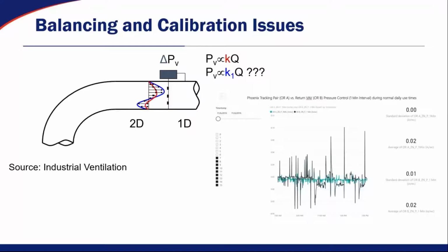Now, if you're taking an average flow velocity with that flow profile versus a nice fixed one in a straight piece of ductwork, obviously there's going to be an inconsistency. So that little chart on the bottom there is looking at the inconsistency of flow measurement as the velocity changes through the ductwork. You can actually see that the velocity pressure is spiking through that device, and it causes delays and it causes hunting in those types of control devices.